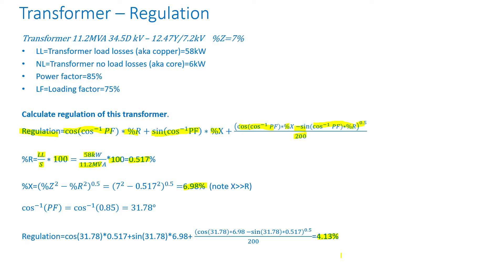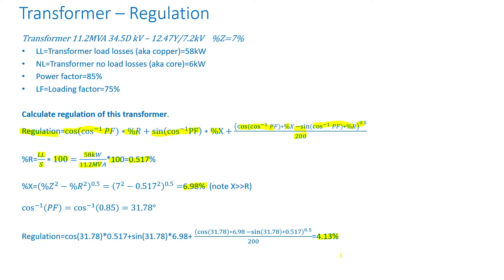Why do you calculate regulation? Regulation tells you basically what kind of taps you need. Like in this case, the regulation is 4.13%, so you would need 5% taps. That way, if the voltage drops because of load increase, then you can increase the voltage properly.